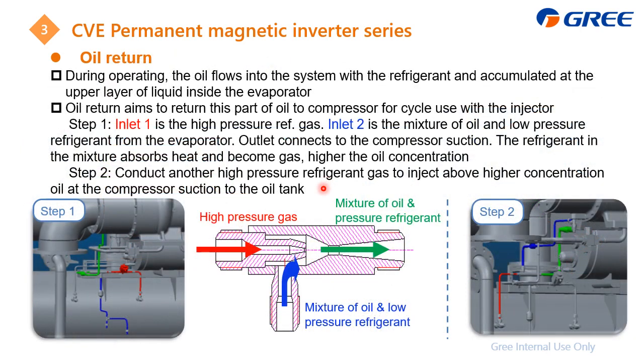Next, we go to the oil return. During operation, the oil flows into the system with the refrigerant and accumulates at the upper layer of the liquid side at the evaporator. The oil return aims to return this part of the oil to the compressor for lubrication, and the key device is the injector, which is this device. Actually it is this one and also this one here, and there are two steps. The first step is for the injector. Inlet 1 is from the high pressure refrigerant, and inlet 2 is from the evaporator, which is a mixture of the oil and low pressure refrigerant.